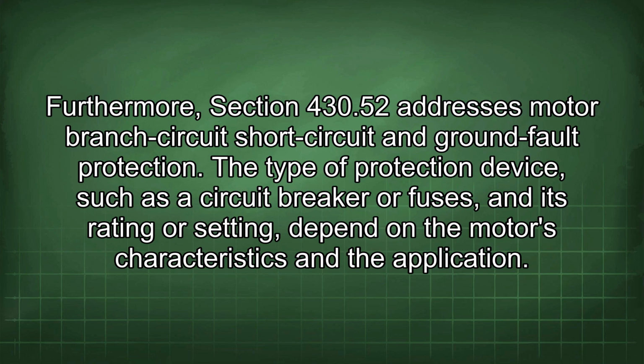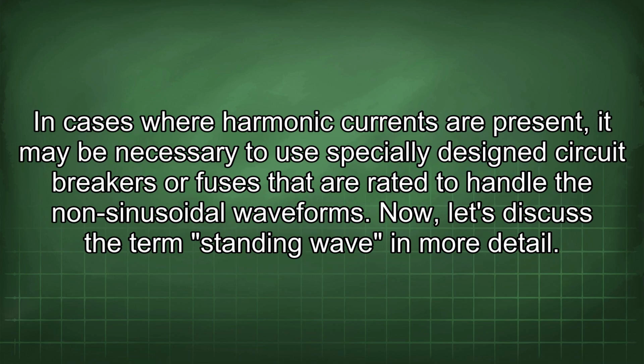Furthermore, Section 430.52 addresses motor branch circuit, short circuit, and ground fault protection. The type of protection device, such as a circuit breaker or fuses, and its rating or setting, depend on the motor's characteristics and the application. In cases where harmonic currents are present, it may be necessary to use specially designed circuit breakers or fuses that are rated to handle the non-sinusoidal waveforms.